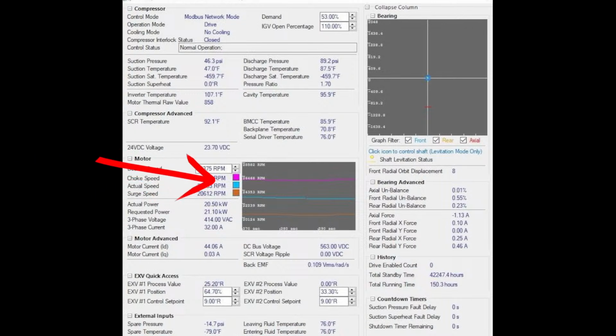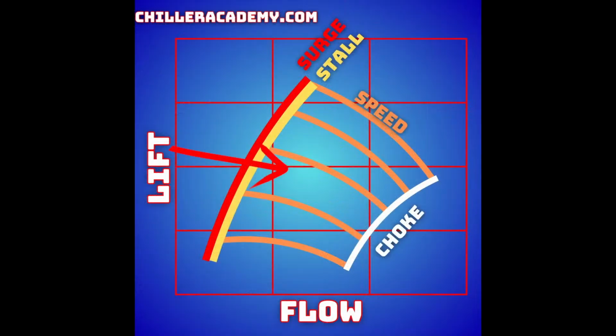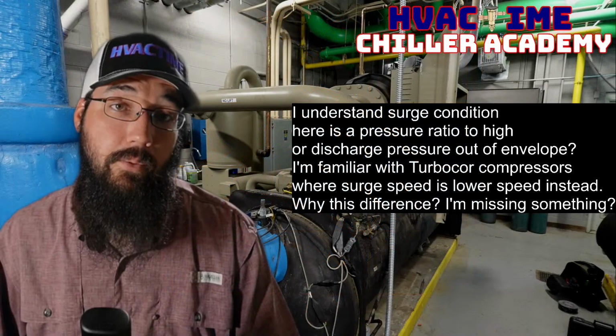Replace speed and RPM with just flow and CFM, and you accomplish the same basic terms, with our ratio being just our lift. So instead of saying lift in terms of, say, saturation temperature, so we have 45 degrees of lift, we're using it in terms of ratio, the ratio between suction and discharge. This ratio helps us determine where we are on this actual graph over here on the left side. So where we're at on this graph, where our RPM is, it's just two ways of saying the same basic thing, is how I would characterize it.